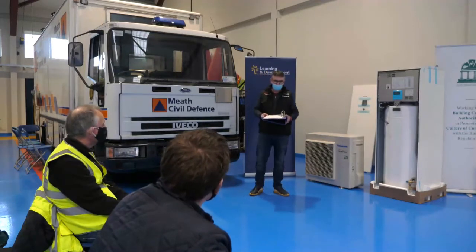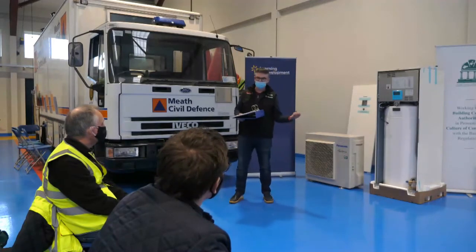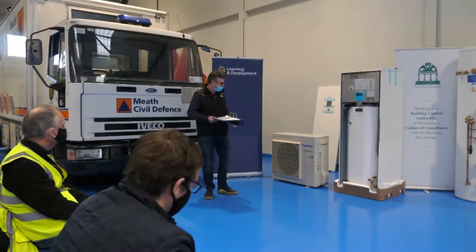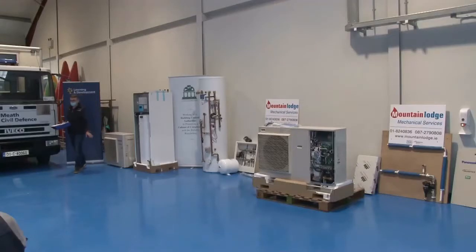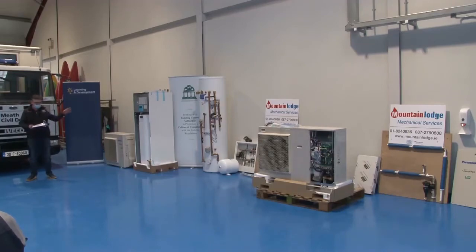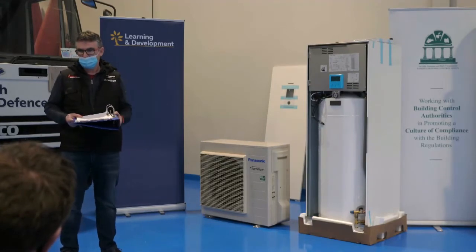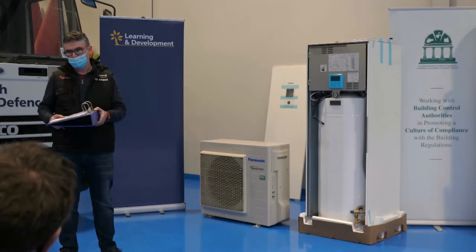So the duct is crucial because if the pipes were just dropped in the soil, it's going to be using up the energy trying to deliver into the outdoor unit. That'd be one thing to look for when you get to the outside. It can be located a little bit further away from the house, because it's not like we're losing the energy straight away, since the compressor's working to inside and inside is starting to generate, but within reason. We can't send it off down the back garden completely out of sight. There will probably be a 20 metre max between the outdoor and the indoor unit, or otherwise efficiency starts tailing off.